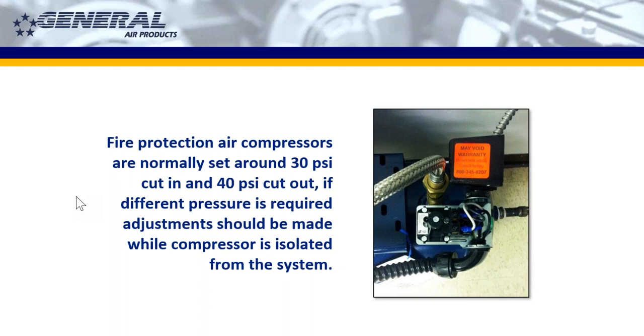Please call us first. We always put a sticker on these pressure switches that says may void warranty, and that's because we want to scare you into calling us. It's not because we're looking to void warranties or anything like that. What we want is, when you pop the cap off of that pressure switch and you're not sure which is the differential screw and which is the range screw, the range screw is the one that you should be adjusting if you decide to adjust the pressure switch.